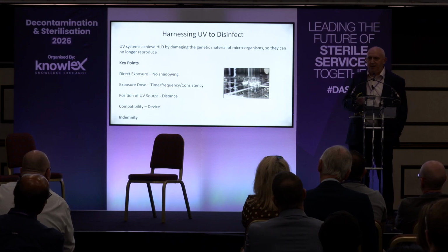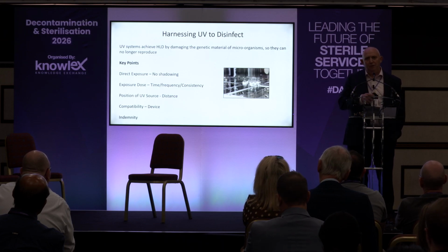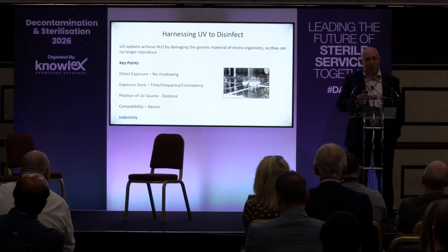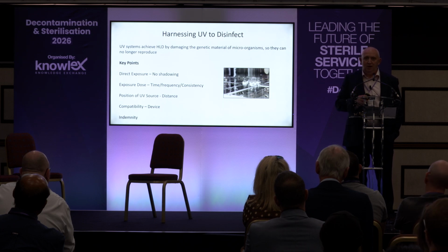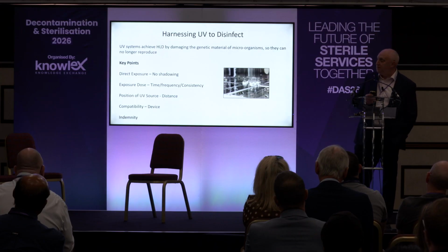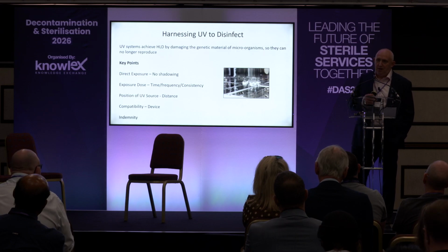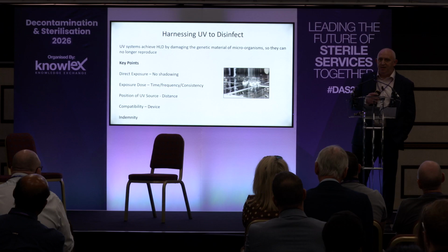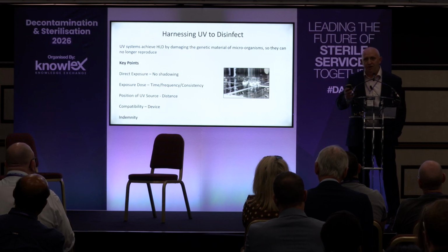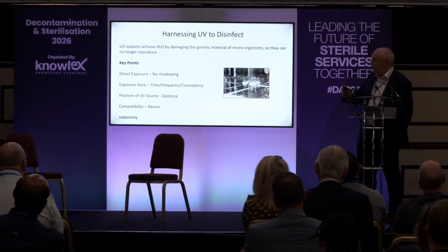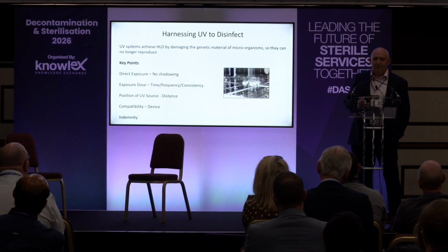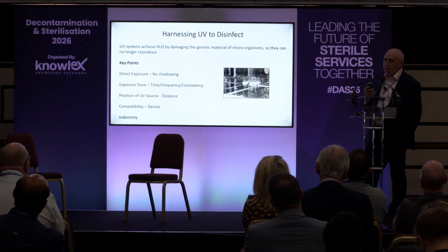Indemnity, something we've been very keen on with suppliers of this type of technology. We need to have an indemnity statement from them to say that if there is any unforeseen damage to a device, they will investigate, and if they are deemed responsible, they will provide compensation. Now, thankfully, we've had a few brushes with that indemnity agreement, but there's not been any major action to be taken on that. But there has been one or two, and when you come to probe damage, whether it be with hydrogen peroxide, UV, it always becomes a bit of a misty debate. So we have to get things correct when we're doing that.